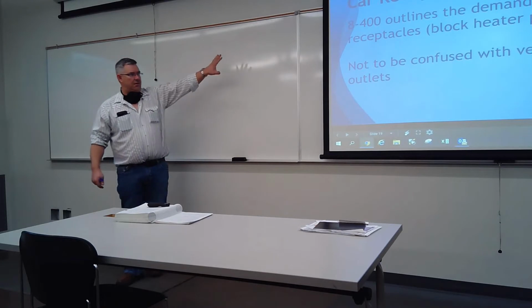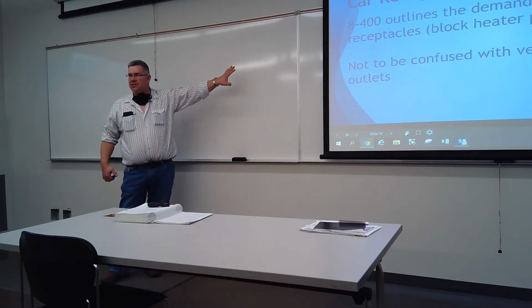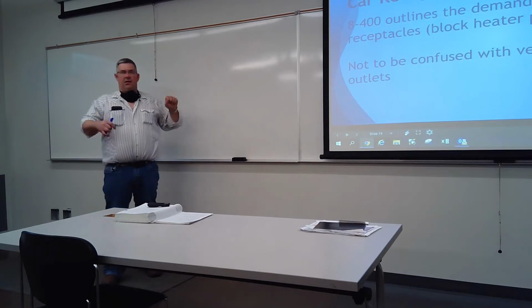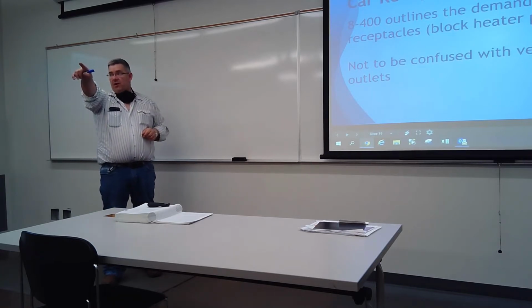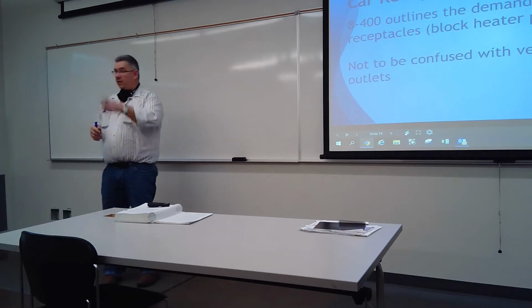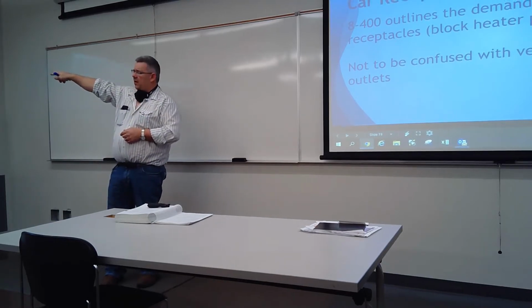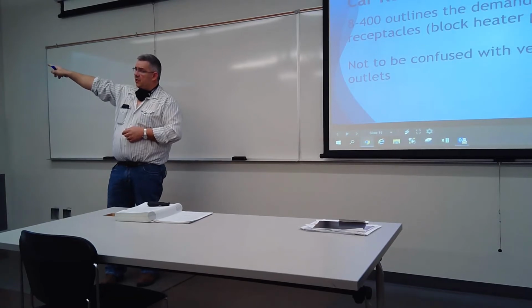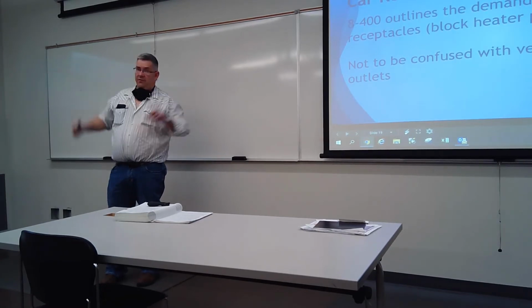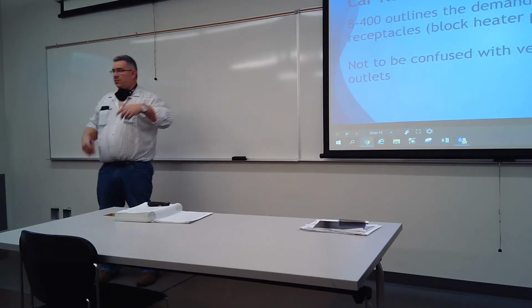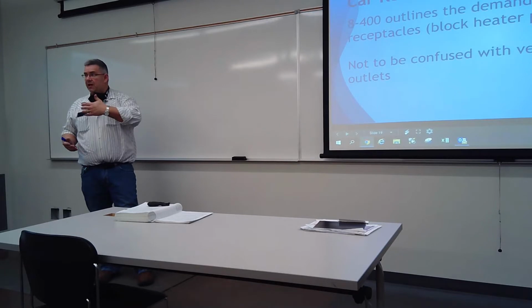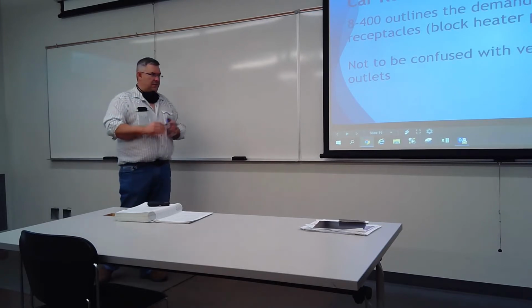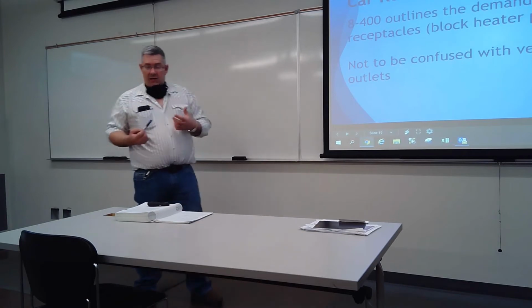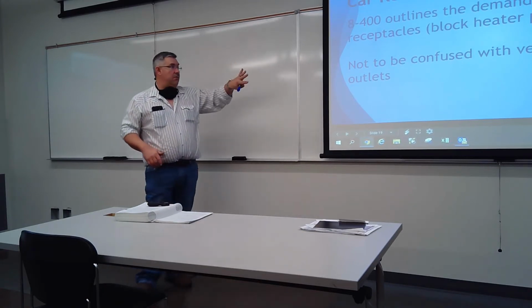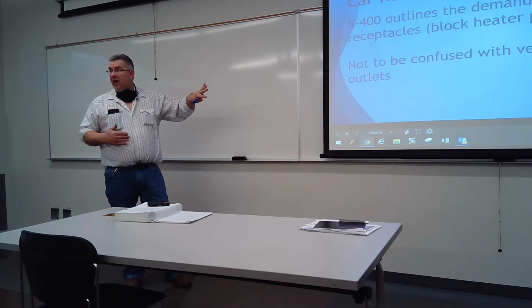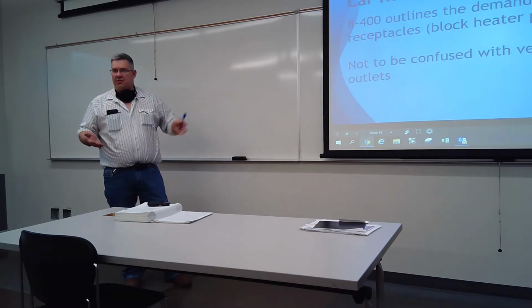So this parking lot out here will be on for 20 minutes, and it shuts off for 40. When it shuts off, the one out behind comes on for 20 minutes, and it's off for 40. And when it shuts off, the one on the other side of the administration building comes on for 20 minutes, shuts off, and then goes through the cycle again, right? So it allows full current, but only a third of the time, and that way they reduce your overall demand. So if you've got a system where they're controlled like that, they have a lower demand than if they're just 15 amp circuits that are powered all the time, right?